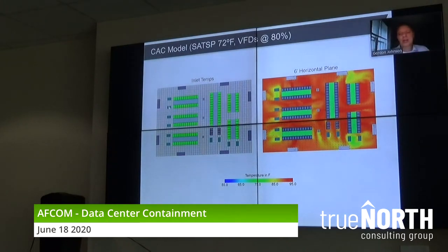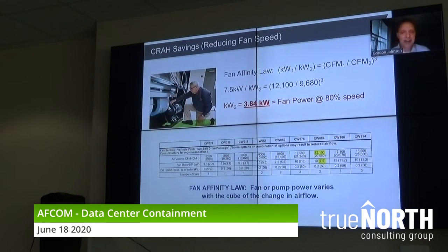On the right, the horizontal temperature plane, the temperature going back to your coolers is now even hotter. They're going to run more efficiently. They're going to give you more cooling. And again, will that data center be a little bit warmer to walk into? It will be. However, let's see how much money we start saving by doing this. The slide might seem a little overwhelming at first glance, but look down at the bottom. The fan affinity law says the fan or pump power varies with the cube of the change in airflow.